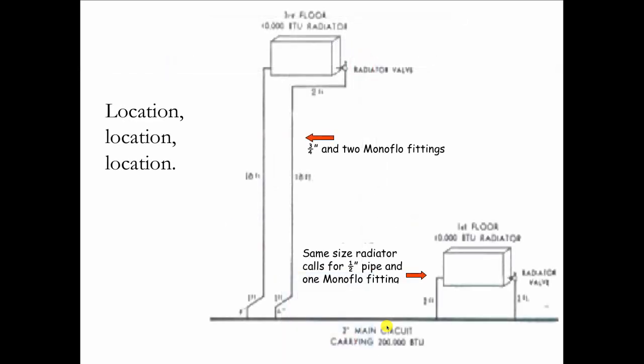This is from Bell & Gossett's design manual from the 1940s. They're showing a 10,000 BTU radiator on the first floor and another one on the second floor. And it's the same radiator, but the difference is on the first floor, it only needs one half inch monoflow fitting to work. That would be on the return side. But if we move that radiator up to the second floor, because the run to it is longer, and the run back from it is longer, we'd have to increase the pipe size to three quarter and use two three quarter inch monoflow tees down here, even though it's the exact same radiator.